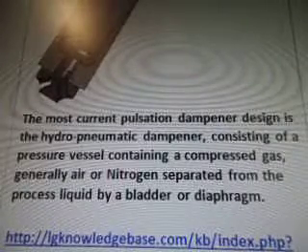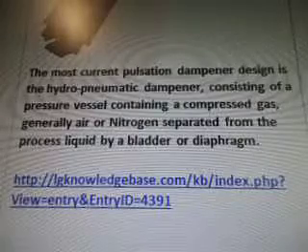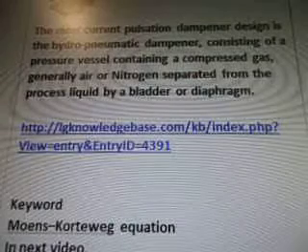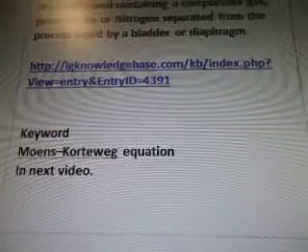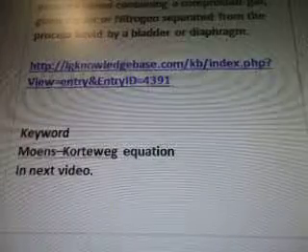The most current pulsation dampener design is the hydropneumatic dampener, consisting of a pressure vessel containing a compressed gas — generally air or nitrogen — separated from the process liquid by a bladder or diaphragm. The keyword Moens-Korteweg equation is going to be in our next video. Thanks for watching.